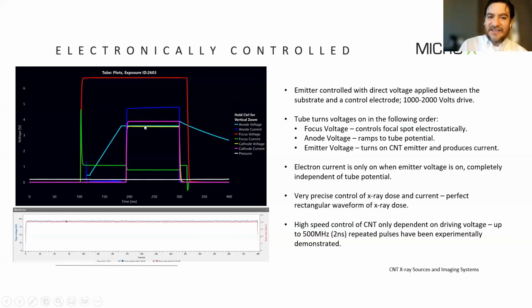And that current makes X-rays. So because of that, we've got a very, very precise X-ray dose. It actually looks like a perfect rect function. So you can actually see here from a RaySafe measurement that the dose and the anode potential follow each other perfectly over the length of the pulse.